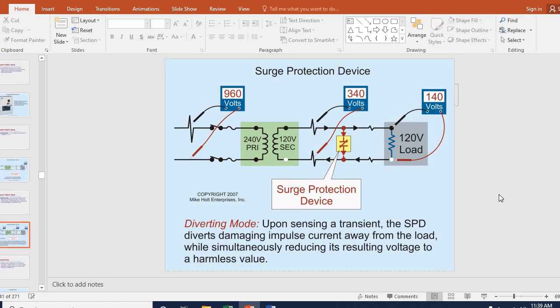Surge protection devices. Just about all your factories have your surge protection for spikes and lightning, and usually it will have a set of contacts that will tell you if it's open or closed. I know a lot of the water and wastewater devices or pump stations have a surge protection and just a phase monitor. If you lose a phase, it will drop your controls out, carry your control voltage through that device. And if it loses a phase on a 3-phase system, it will drop that control voltage out and open up all your starters where it don't damage your motors.